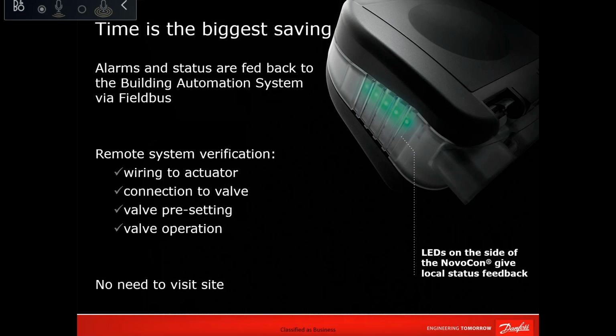But if you link it with BMS, with the looping, then it will be a more expensive solution, and you need to select which area to use this Novocon. In shopping malls, we use it everywhere because it's most of the time linked with the owner. But in the case of a residential building, where the delta T is really crucial for the overall consumption of the building, then yes, a solution can be to make the Novocon a standalone delta T manager. So you will not have the monitoring feature, but you still have the energy management feature. But the monitoring can be there if you want to locally visit the Novocon. You can link with our configuration tools and see all these variables live in front of you.